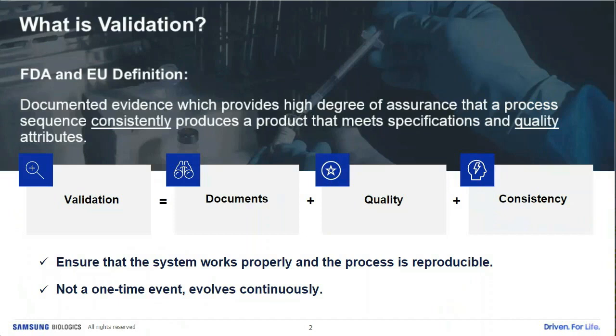Just to give a recap on validation, what is validation? For those new to validation or with experience, it's documented evidence which provides a high degree of assurance that a process sequence consistently produces a product that meets specifications and quality attributes. Validation could be anything from the utilities, the facilities, the equipment, to the process itself. We want to make sure the system works properly and the process is reproducible.